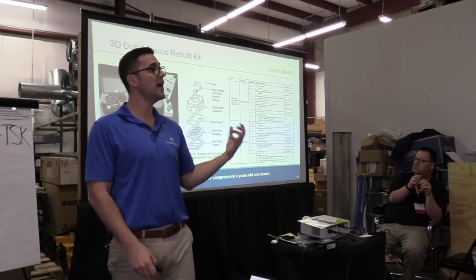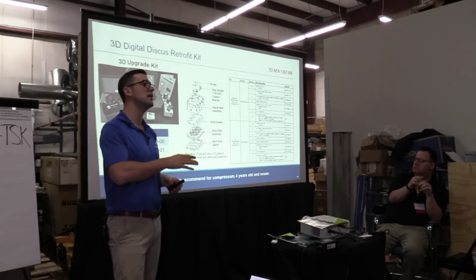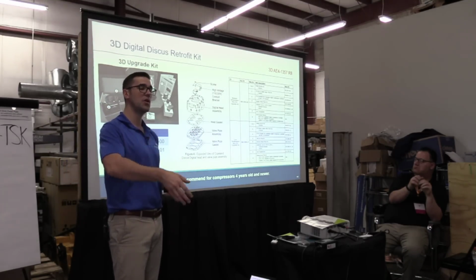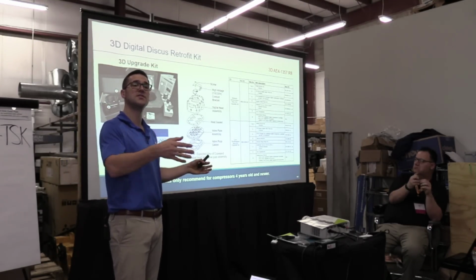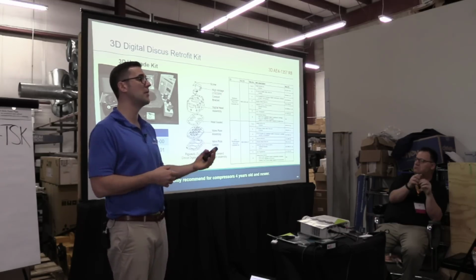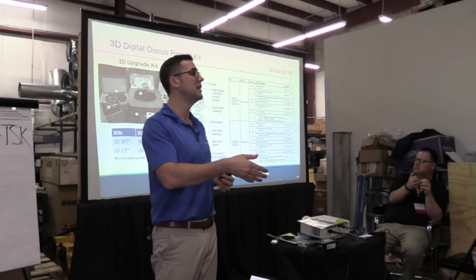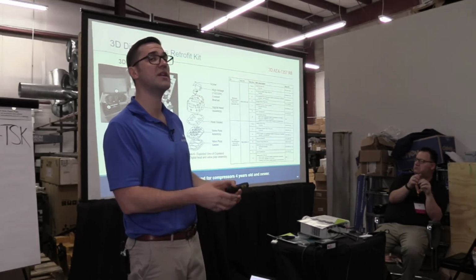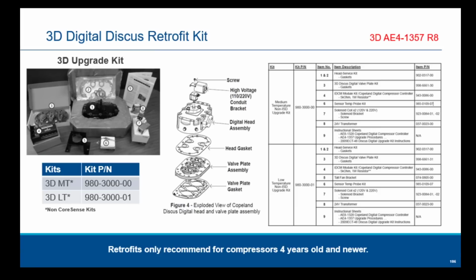One cool thing about the digital compressor is you can do retrofits, so you don't have to pull the compressor out. We've done tons of white papers where, if there's a 20-year-old compressor, you find the worst compressor on the rack. So you use Copeland Mobile. Which one's running the hottest? Then you pull it out and put a new compressor on without even activating a digital. You're going to get a 4% efficiency gain because you're going from an old compressor to a brand new one and more work is done. But then you activate a digital on there, and we see upwards of 12 to 15% savings, depending on the application.